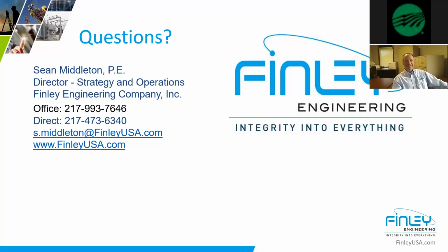Another thing, it happens to be close to a transmission substation. We happen to have fiber there. So we're going to use the fiber from our relays into the station just to trip that breaker that's under our control. And you can imagine trying to send that trip from us to them. We have to count on them to maintain their equipment, to maintain their controls, and to count on our signal getting to them and their equipment tripping. And once it gets to that point, how well can you trust it?